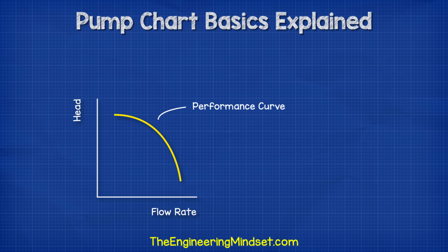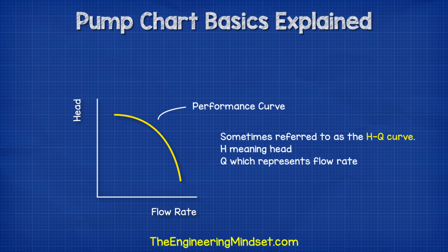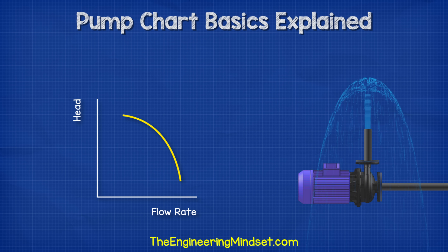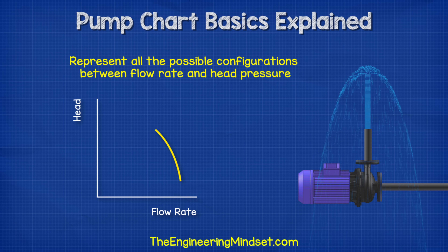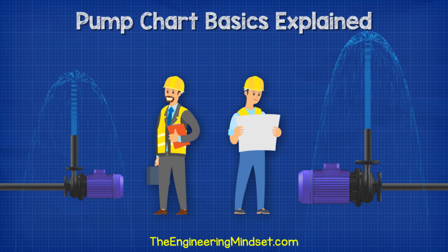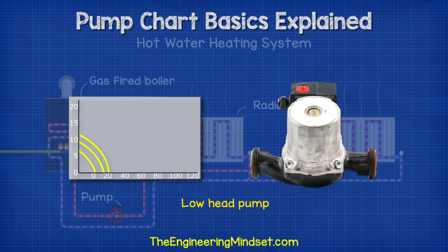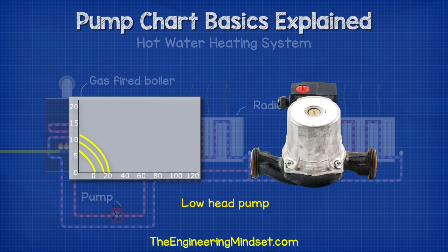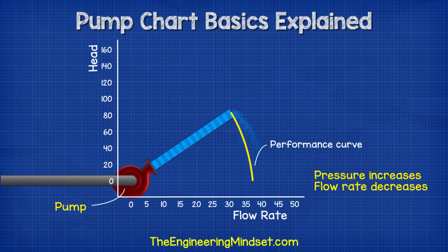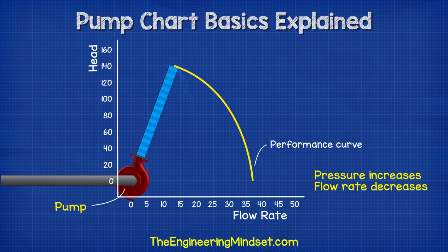Performance curve. This is sometimes referred to as the HQ curve — H meaning head and Q which represents flow rate. The manufacturer will test each pump to obtain the performance data and then plot this on the graph. This will represent all the possible configurations between flow rate and head pressure and we use this to check whether a pump will suit our requirements. The performance curve will be different for each pump and some will suit our system needs better than others. You will usually see that as the pump flow rate increases, the head pressure decreases.